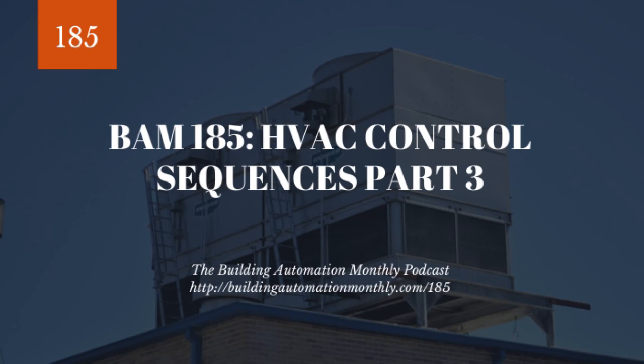With some systems, we'll actually look at enthalpy, which factors in the relative humidity of the air and the moisture content of the air. And by doing that, we'll make a decision: is the return airstream more humid and more moist than the outdoor airstream? And if it is, then we're going to close down that return airstream and utilize the outdoor airstream, because the mechanical effort of our system to remove that moisture is going to be lessened by making that calculation. So that's economizer control for a cooling scenario. And I'm looking at the time here and realizing that we're probably not even going to get into mixed air units of variable air volume. I just think we're going to run out of time, but we'll try.